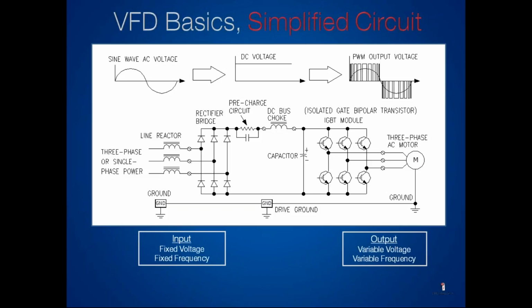The IGBTs are looking at that DC voltage. They know what speed our motor wants to be run at. And those IGBTs are releasing voltage in pulses. It's very steadily releasing voltage based on a certain time, and that timing is based on the frequency that you want your motor to be running at. So in this case, let's say we want our motor to be running at 30 hertz. We're going to run that motor pretty slowly. Those IGBTs are releasing that current in a 30 hertz fashion. This is called pulse width modulation. Pulse width modulation is a very common term. Many other drives utilize the pulse width modulation terminology or technology.